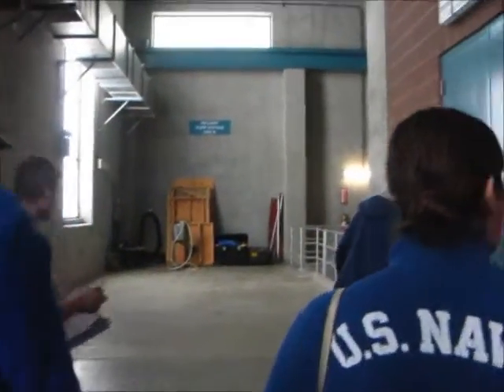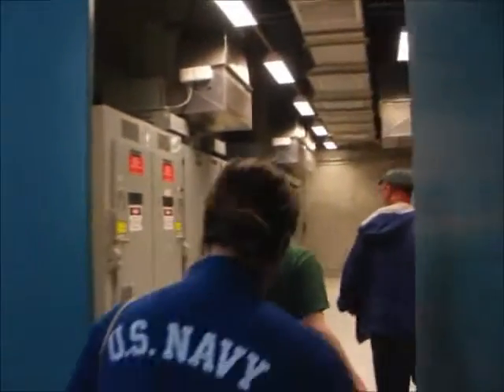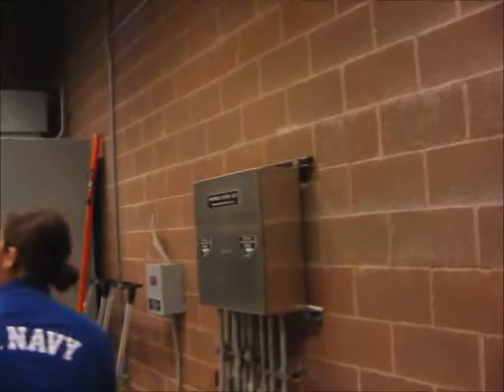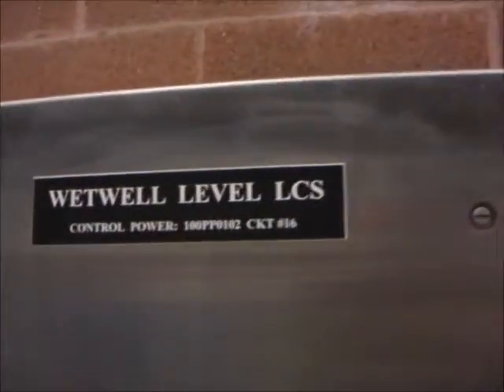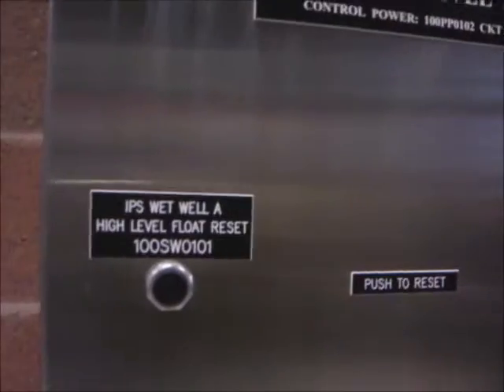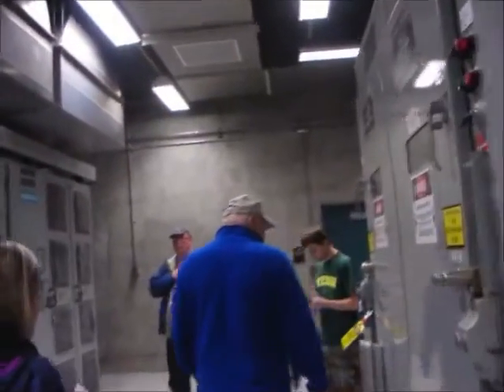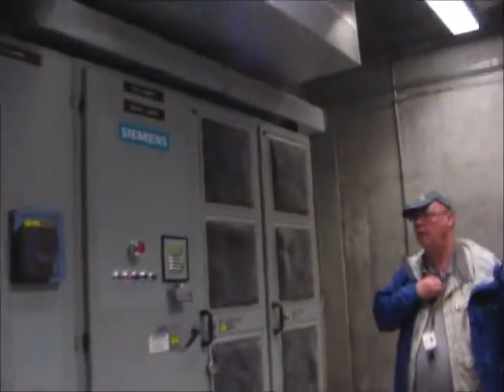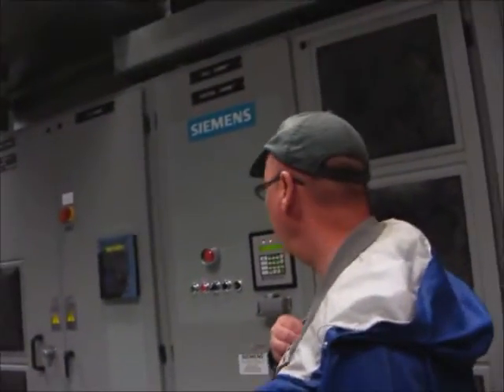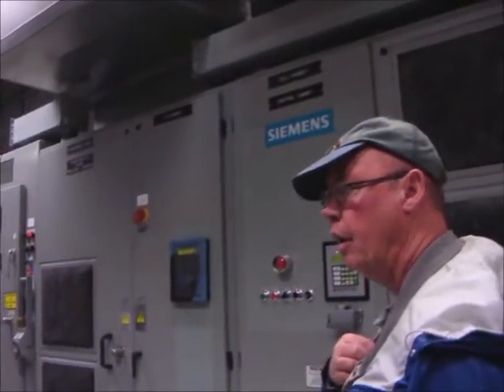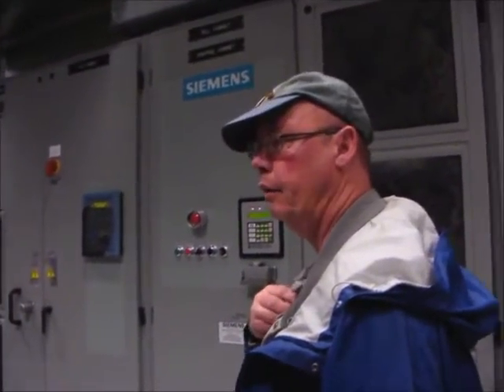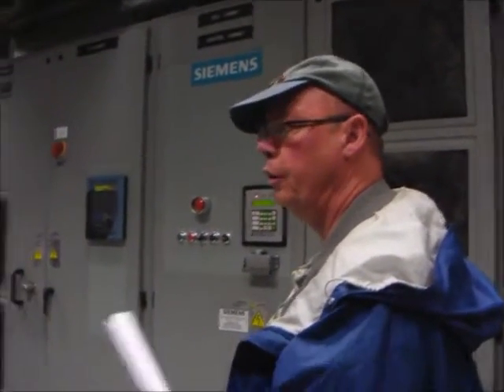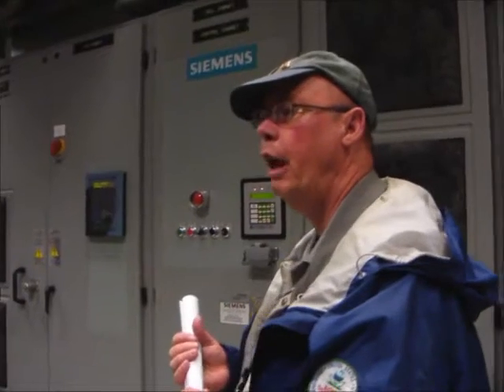On the other side over here, these are the variable frequency drive motors. It ramps up the pumps on the wet well depending on flow coming into the plant. So again, here's the wet well level. There's your flow bubbles for A and B, one side versus the other. Siemens here, influent pump. So pretty much everything in the plant is monitored by the PLCs, and we can run most any part of the plant through numerous terminals that we have throughout the plant.